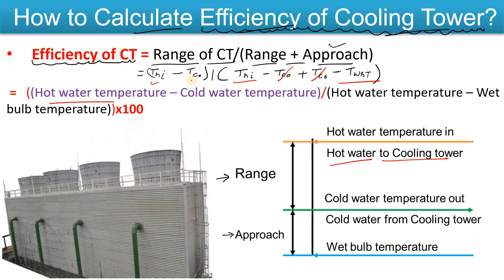So the final formula for cooling tower efficiency is: (T_hi minus T_co) — which is also known as the range of the cooling tower — divided by (T_hi minus T_wbt), multiplied by 100. This gives you the efficiency of the cooling tower as a percentage.